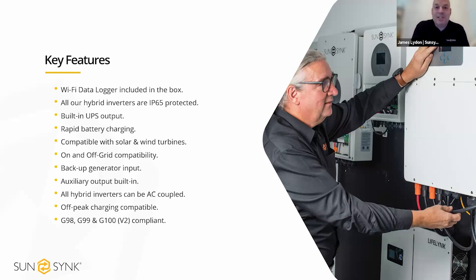All of our hybrid inverters are IP65 protected, so they can all be installed outdoors, no issues whatsoever. They all have a built-in UPS output. As you know as installers, with a standard PV system or a hybrid system with a battery, if the end user has a power cut, they will not be able to access the power from the PV or the batteries unless it is wired in a certain way, such as with a gateway. But with our inverters, we have that dedicated output built in, so anything physically connected to it will remain powered if there is a power outage, which negates the need for a gateway, and it works quite well.